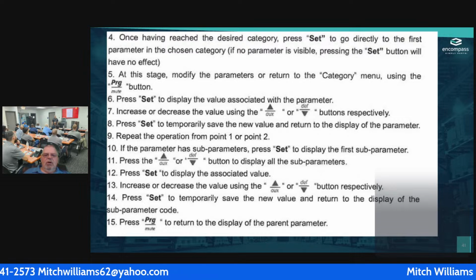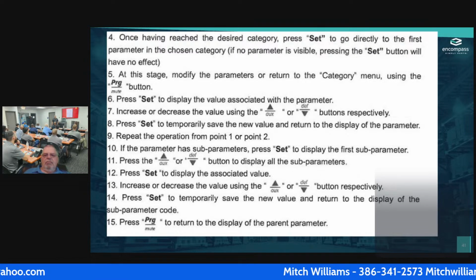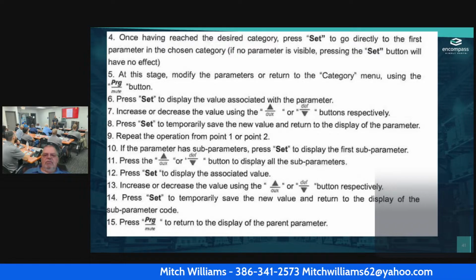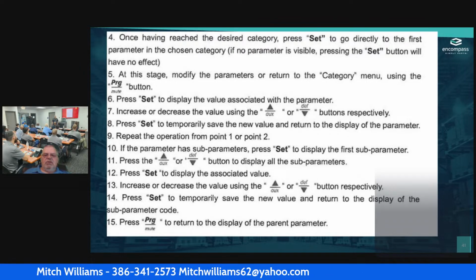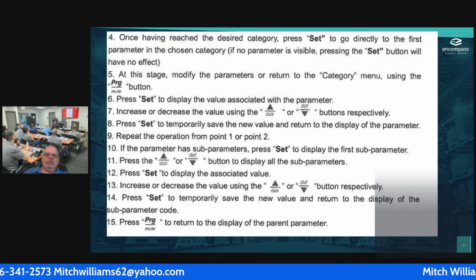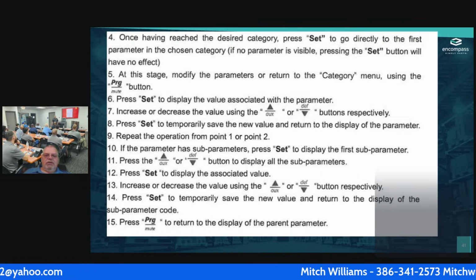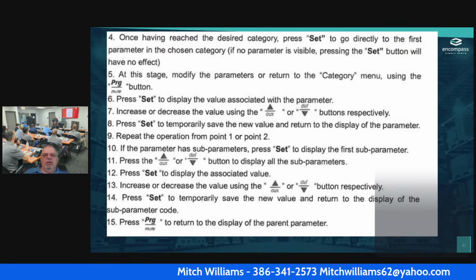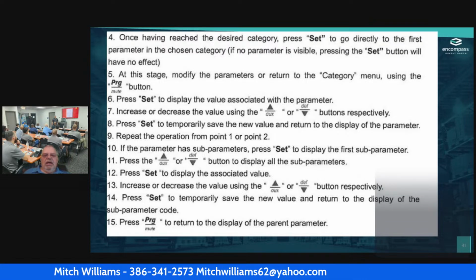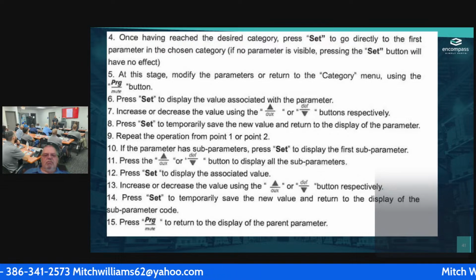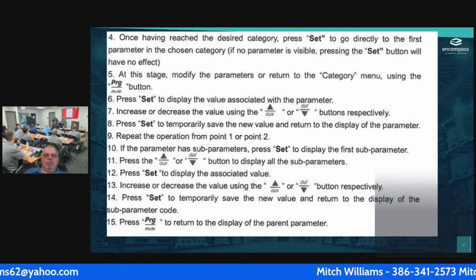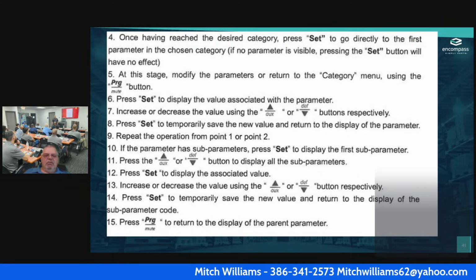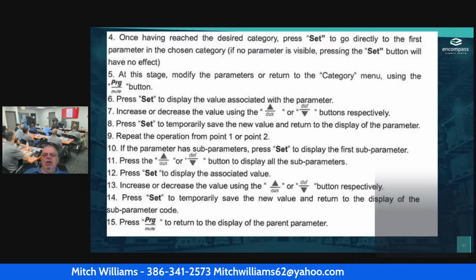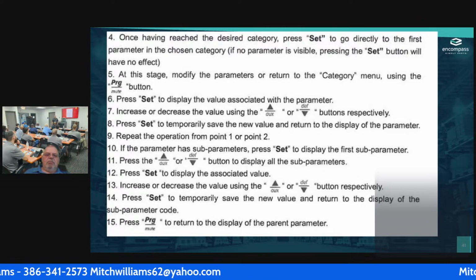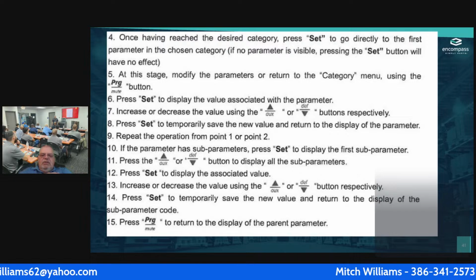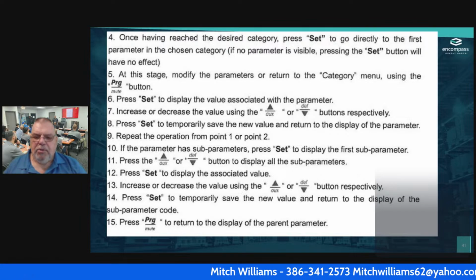If the parameter has a sub parameter, press the set button on the display for the first parameter. Then press the up or down button to display all of the sub parameters. Press the set button associated with the value. Then I can increase or decrease that value by using the up or the down arrow respectively. Then I can press set to temporarily save the new value and return to the display of the sub parameter. Then I can press program to return to the display of the parent parameter.